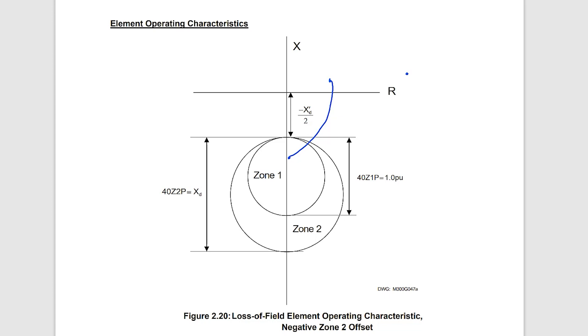For the more severe case when the machine is heavily loaded, the impedance is closer to the origin after the loss of field condition. In real-life applications, this impedance will ultimately land between the average of the direct axis and quadrature axis sub-transient impedances at the low end for the heavily loaded case, and between the direct axis or quadrature axis synchronous impedance at the high end for the lightly loaded or unloaded case.